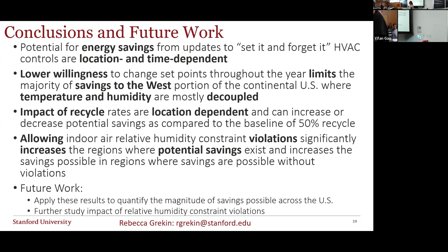I was just interested, perhaps I missed the definition of savings. What would be a counterfactual scenario? Let's say I want 0 violations, what would that be? So this is an example: I'm calculating the chilled water load with my model if I kept it at 55, and then calculating the chilled water load if I bring it up to 59, and doing 55 minus 59 over 55, times 100 for percentage savings. And then I'm actually normalizing over the number of days which you would actually see the savings. So here you have the savings whenever the AC is on. The savings on any given day is actually much higher than those numbers I was showing, but I'm normalizing for the number of days where those savings are actually seen, so they change. In New York, basically you see savings two days a year, but the savings you see is almost 60%.